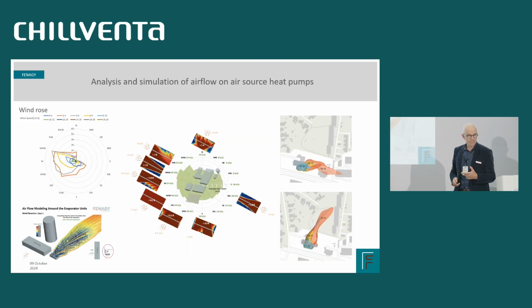So, challenges, what we see. Of course, when we do air source heat pumps, one penalty we could have is defrosting. During wintertime, we have to defrost. But another penalty that could appear is what we call cold air recirculation, meaning that the air that we just cooled down is recirculating back into the same evaporator, and we try to cool it again. And in that way, at the end of the day, we could create a lot of cold air around the energy collectors, and the COP and the capacity will be very poor.